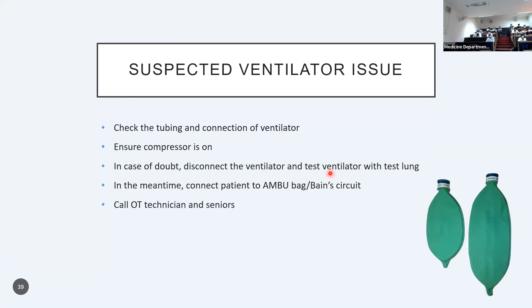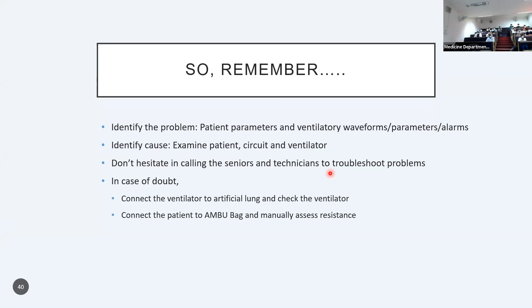Okay. So remember, while troubleshooting problems, identify the problems. How will you identify? By observing both the patient and the ventilator: ventilatory waveform parameters as well as alarms. Identify the cause. Don't hesitate in calling seniors and technicians. And in case of any doubt, you may disconnect the ventilator and check it with an artificial lung, or you may connect the patient to the Ambu bag to manually assess the resistance.